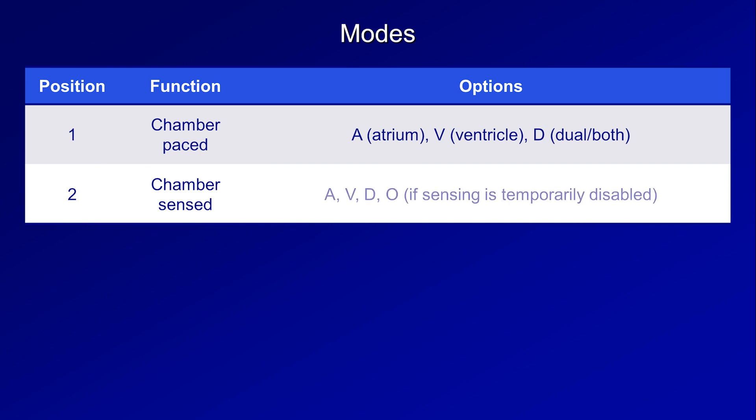The second position is for the chamber whose electrical activity is being actively sensed by the device, where options include A, V, D, and O if sensing function is temporarily disabled.